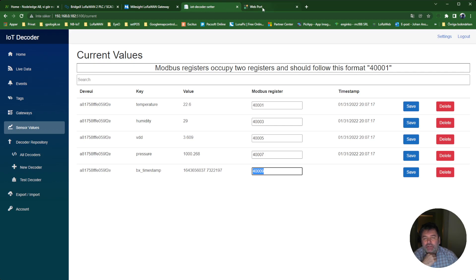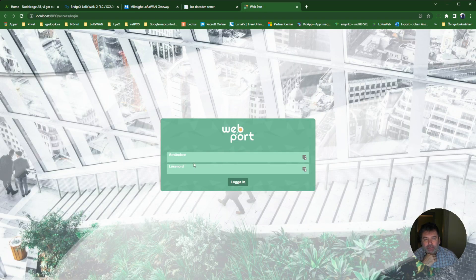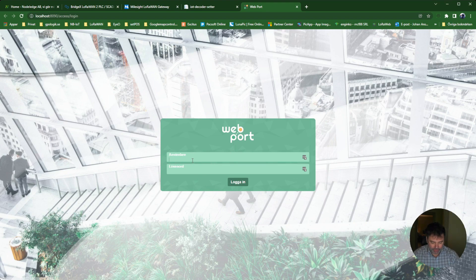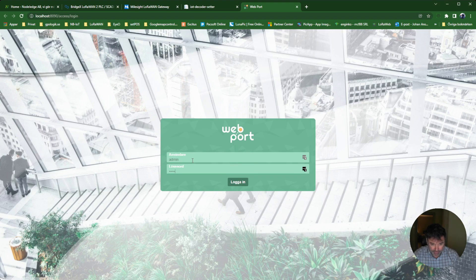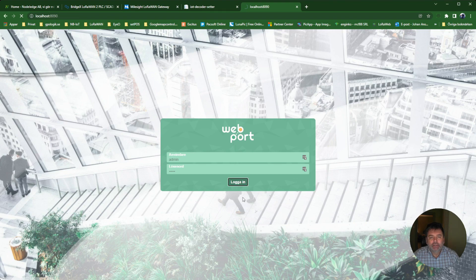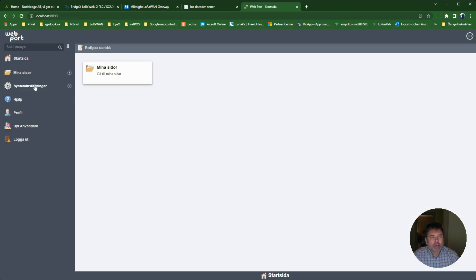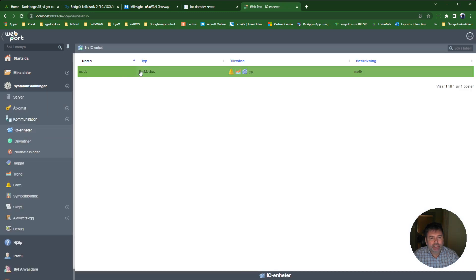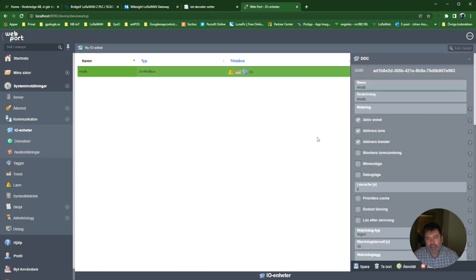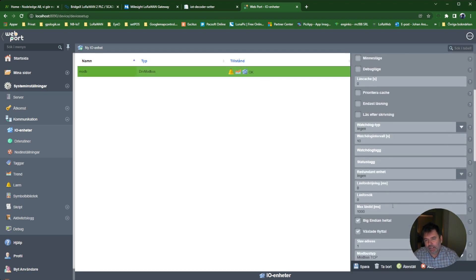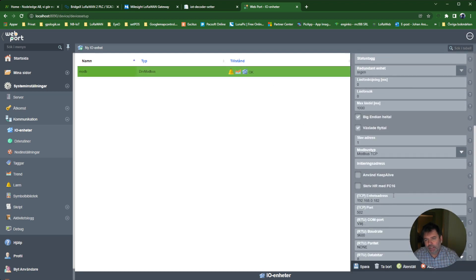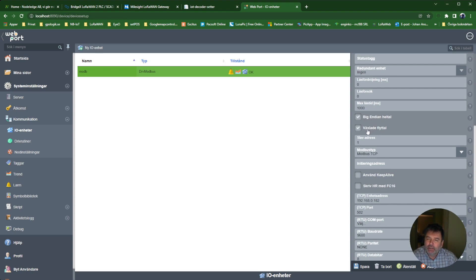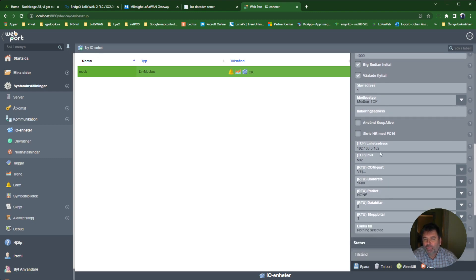Let's go into WebPort, a Swedish SCADA system for buildings. I'll just log in here. I go to Communication and IO Units. I can see that I have the Drive Modbus running here. If I click this, I can go down here to see that we are running in Big Endian and Shifted Float. We are connecting to this IP address on port 502.